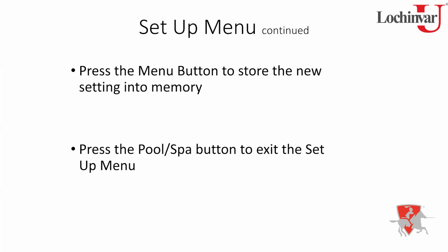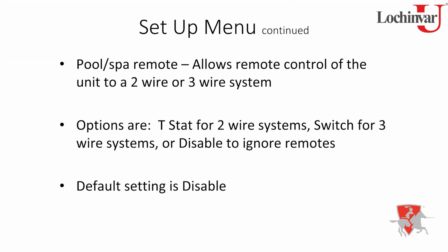So go back in and get into it, then exit out of the menu and it'll store that parameter. Exactly. So just make sure you press that Pool/Spa button to save your parameters once you get done. Now, as far as the parameters go, there's not a lot of them. The first one that you're going to see is the Pool/Spa remote. So this goes back to that terminal strip, the R, the WP, WS terminals.